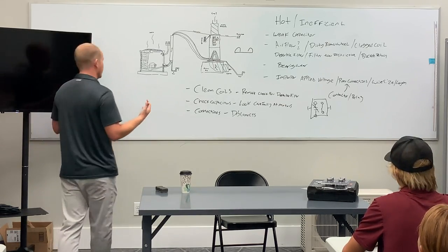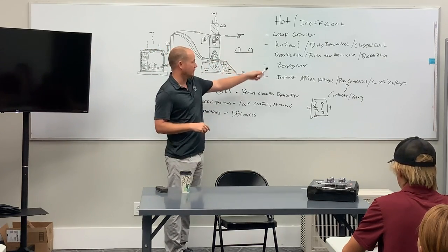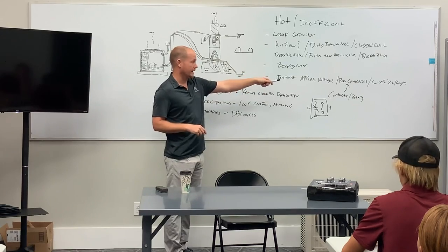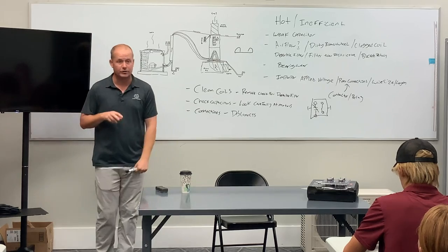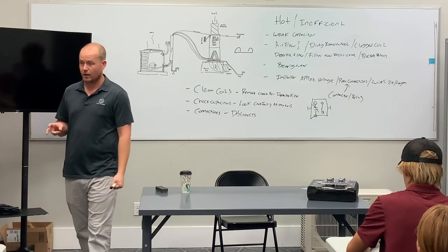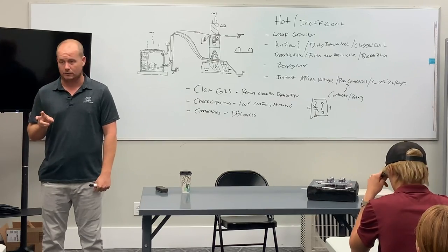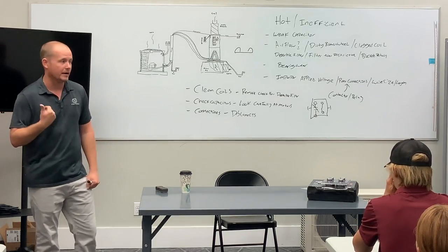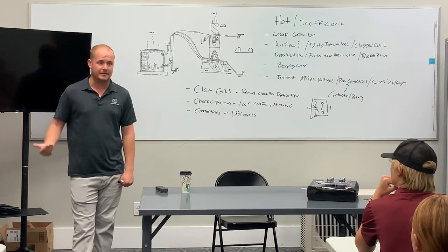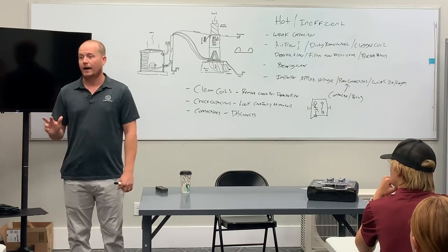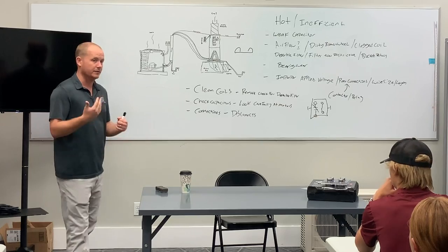So, in terms of summary, things to look for, things that cause hot and inefficient motors: weak capacitors, airflow problems, bearing wear, poor connections. Now again, in terms of something that I want you to check regularly, I do want you to check the voltage on equipment while it's running. That is a really good test to do. In fact, it's more practical for most purposes than even measuring amp draw, because it's very rare that we're going to replace a component strictly based on amp draw. But often you will find low or high applied voltage, and that's something to investigate further.